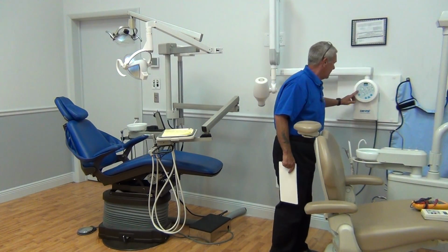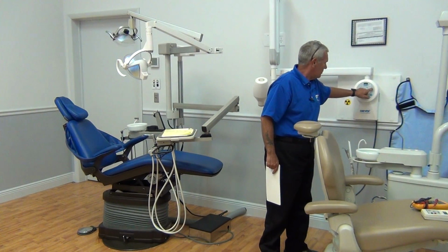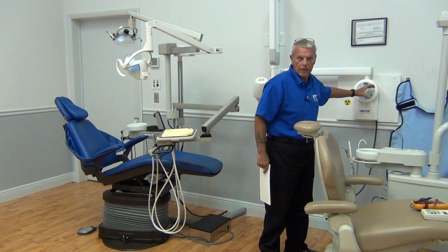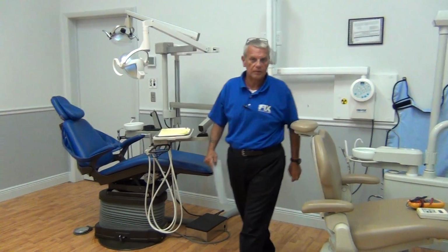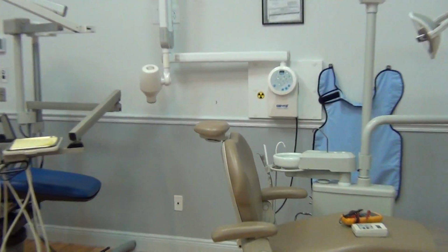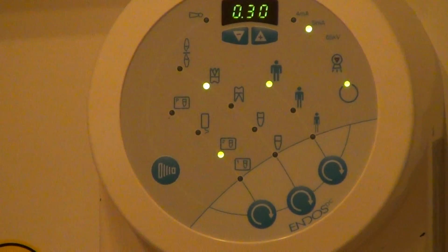Also, on the x-ray, there's an icon that will light up. It'll usually look like a x-ray, a radiation symbol that will light up during exposure. That's called a luminosity guard. It must remain illuminated during the exposure. We're going to concentrate on the x-ray fascia while we make the exposure, and you'll see an LED light up. Did you see the amber LED briefly light up for the duration of the exposure? This is what the inspector's looking for.